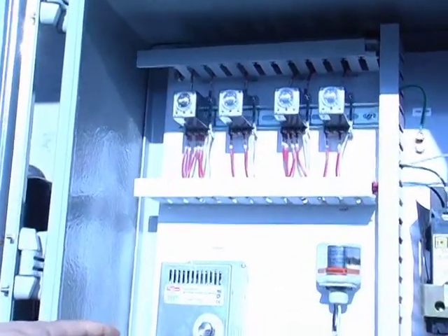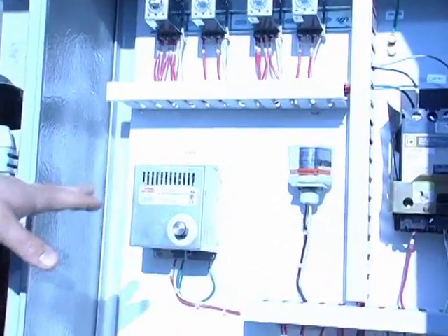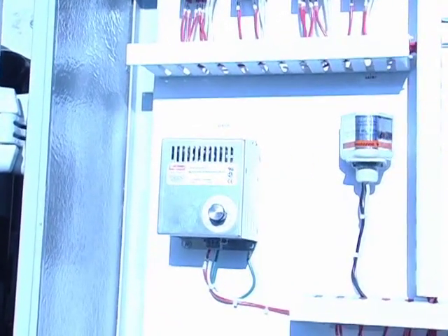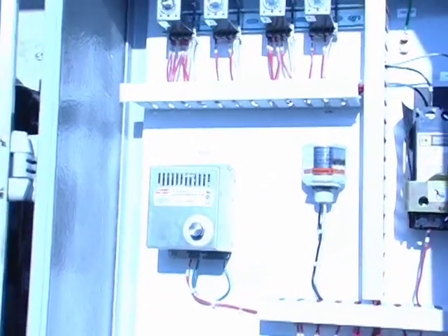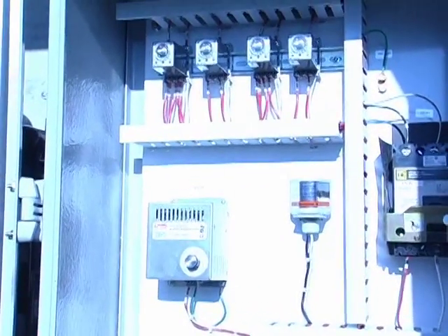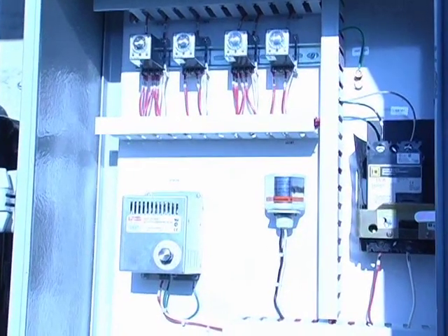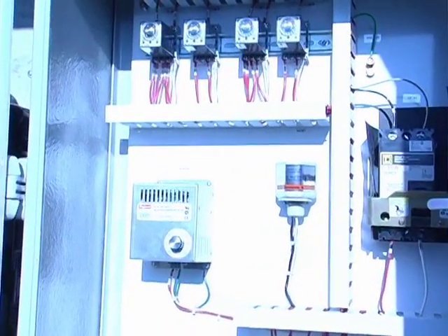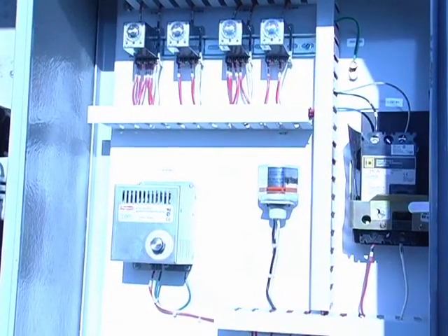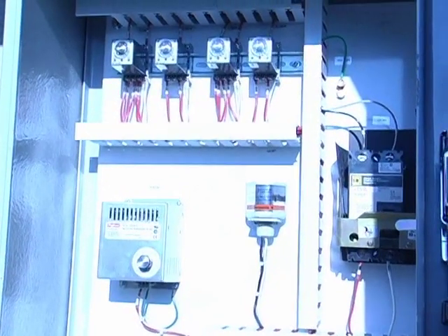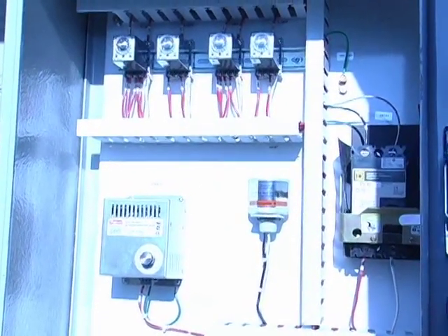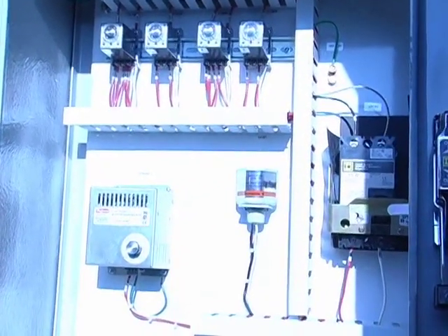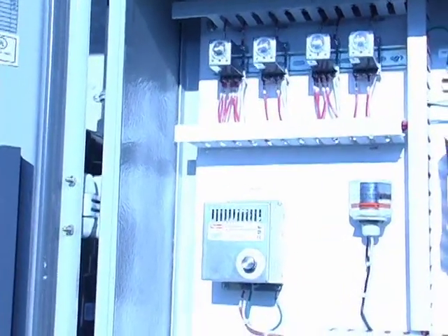And in here, nothing really needs to ever be adjusted, but you do have an adjustable panel heater here. But this is an enclosed cabinet, and that panel heater is, I think, more for the purposes of reducing any condensation that you might see in a panel. I'll go over the humidification sump with you after we turn this on, along with letting you take a peek in the pre-humidification chamber, and watch the upper irrigation nozzles work, and you can kind of see the flows and the pressures that you'll be seeing in the upper and lower irrigations here. However, I don't think we will be turning on the blowers this morning. So we'll close this up.